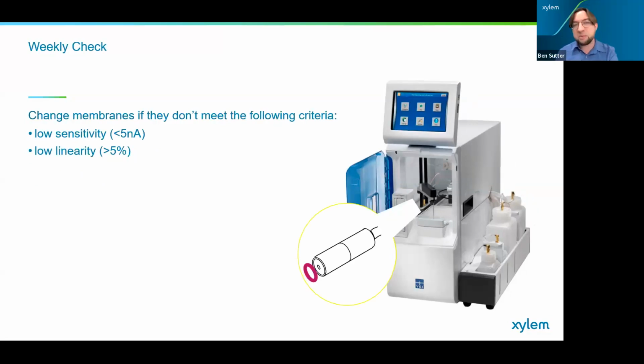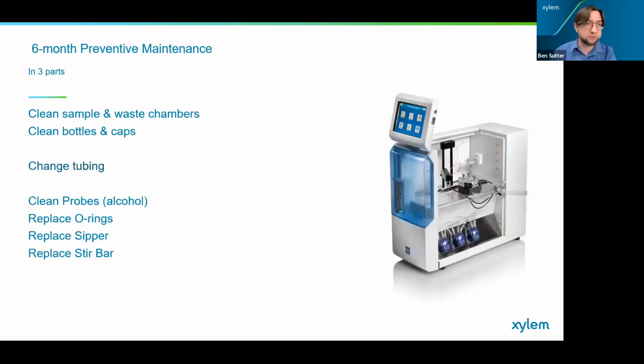Every week, and it may not be every week, but in general, the weekly is about how often you should check this, you should change your membranes if they don't meet the criteria that are on the screen right now. If its sensitivity can't get up to where it needs to be, that is above 5 nanoamps or so, then it probably needs to be replaced. If it has very low linearity and it's not able to keep that linearity, it's also time to give that a replacement. Every enzyme, every type of sugar that we measure will have its own interval. That's all clearly listed in the manual, so make sure you go by those guidelines. And if you notice it's dipping below these criteria, please take action and replace those membranes.